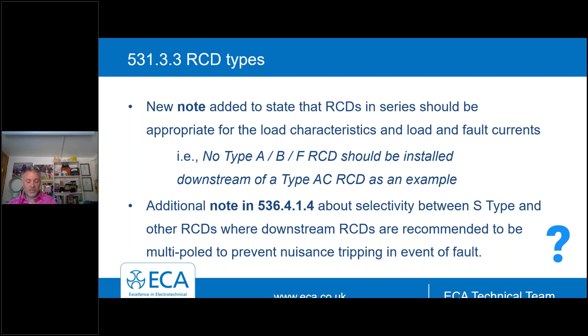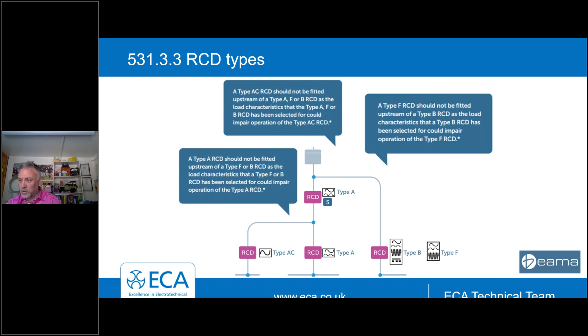For a long time our friends at BEAMA have had a really good diagram on where you should select and erect RCDs. You can see that Type B's and Type F's are nowhere near the Type A's. This is a great download from BEAMA—they've had this in their RCD handbook for a while, confirming good selection and erection of RCDs, and this is now mirrored in Amendment 4.